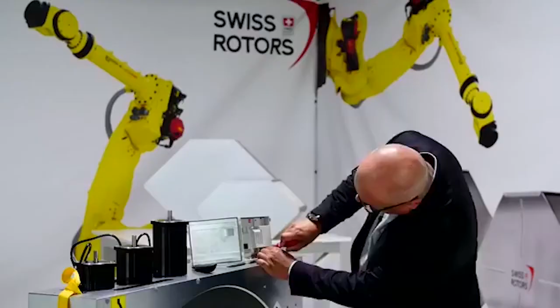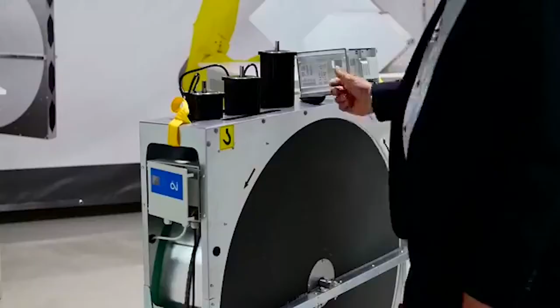If you would like to have this controller not inside our casing, the cable which we provide is 2 meter and 3 meter long. So you can just unscrew those 4 screws and take it out to your panel outside of the air handling unit, I don't know, close to the inspection side, or on the back of the air handling unit, or on the top. And then you can just unscrew those wires from the terminals, because the motor is 3-phase, 200 volts, and the frequency is from 0 to 400 hertz. So you can unscrew this, install this control box wherever you want, and then connect it again. Okay, let's go for the next.